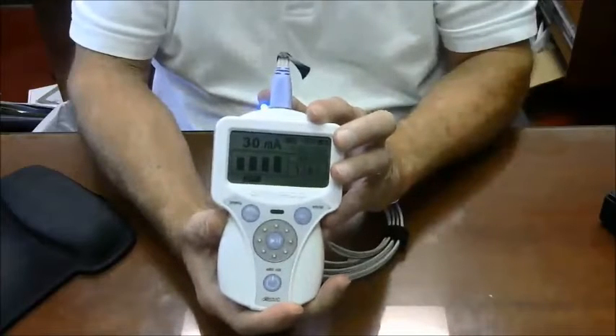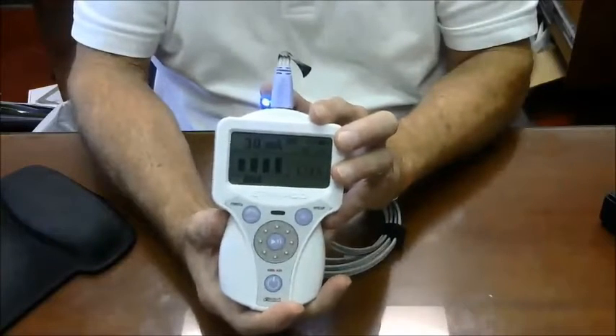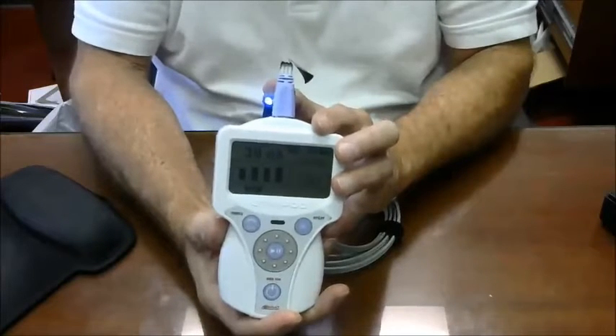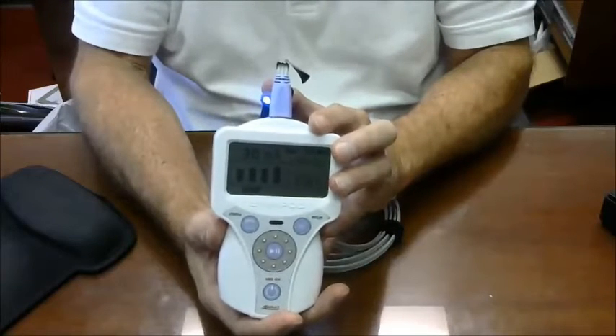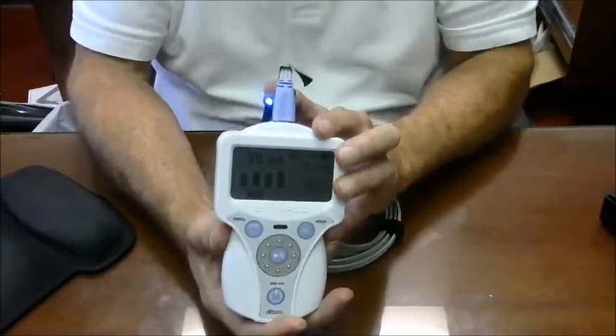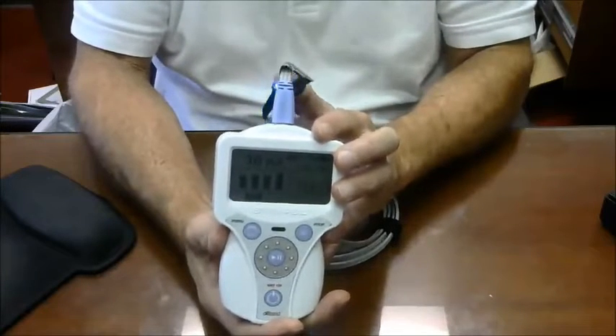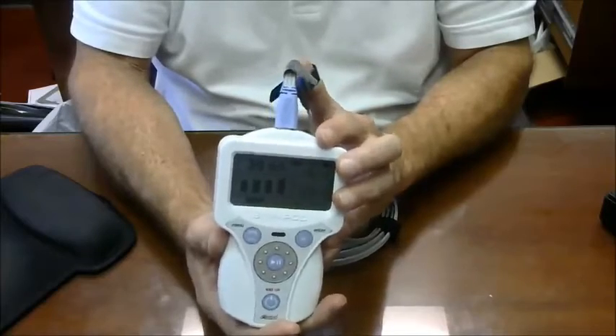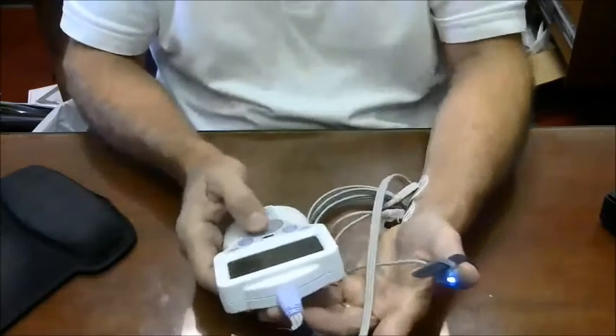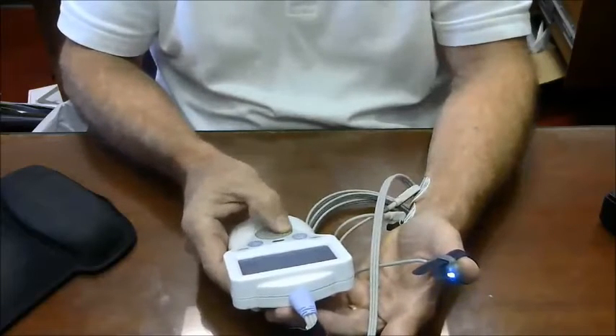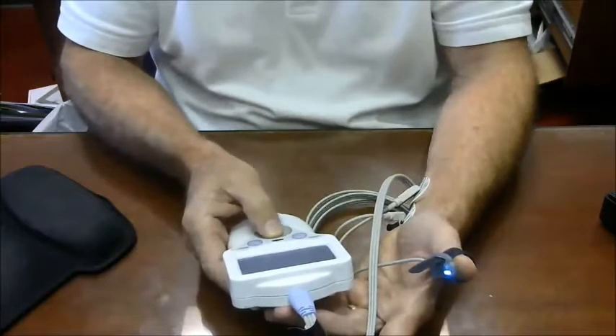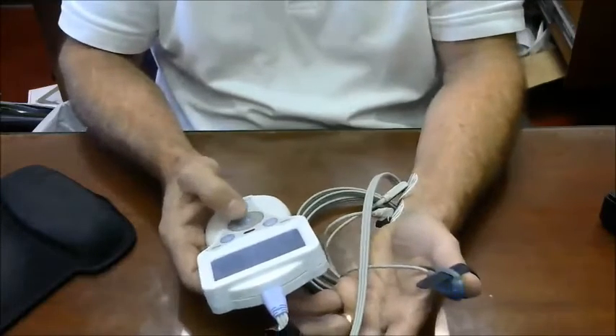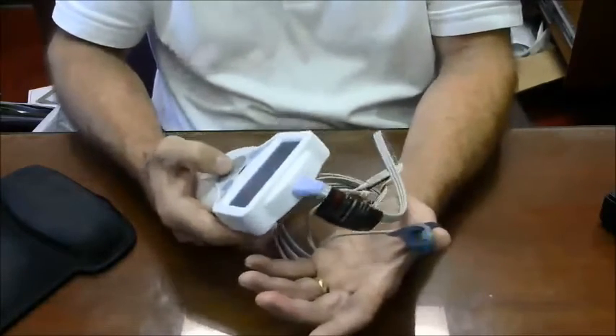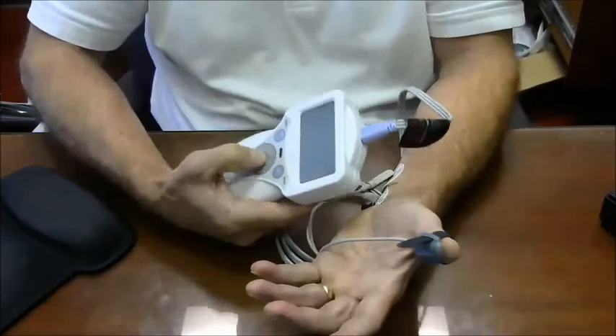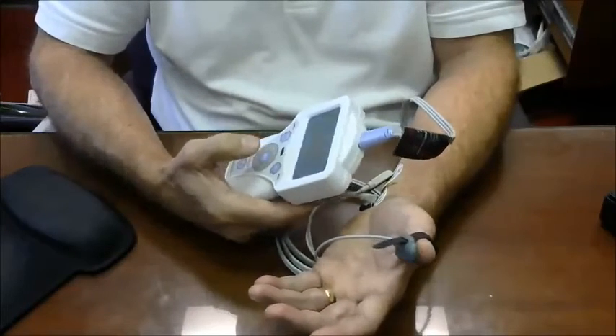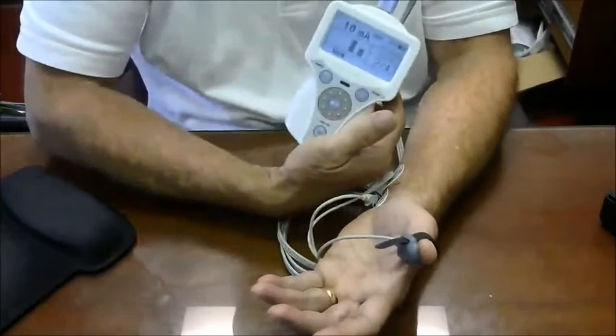There's another thing to be aware of. The reason why we provide you with the bar graphs is if one of the bar graphs was really low or really high in the middle, for example, it would tell the user that maybe there was some artifact there. Maybe the surgeon leaned on the arm as it's being tucked, or somebody bumped into the accelerometer as it's being used. I can also demonstrate, if I go down to like 10 milliamps, which is really low, I can make the accelerometer move myself. So there I just did 2, so that shows 2 of 4.